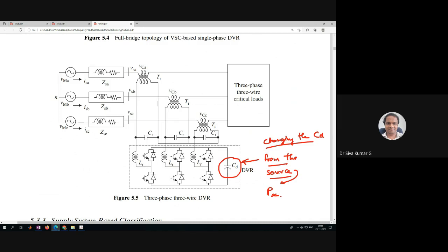And this device, in order to correct the voltage at the PCC, we know is injecting real power as well as reactive power. While considering the real power injection by this particular device, consider only this. Mainly the Q doesn't have any kind of problem. The P is the only problem.